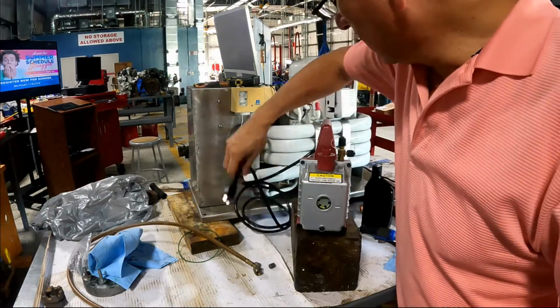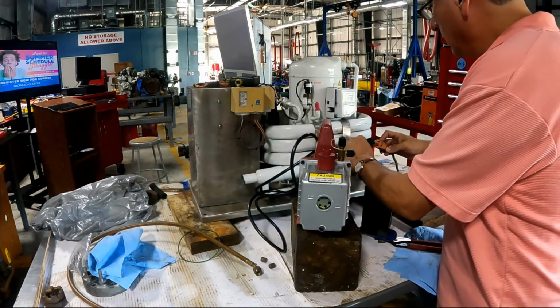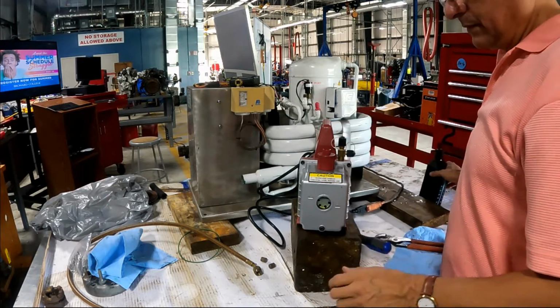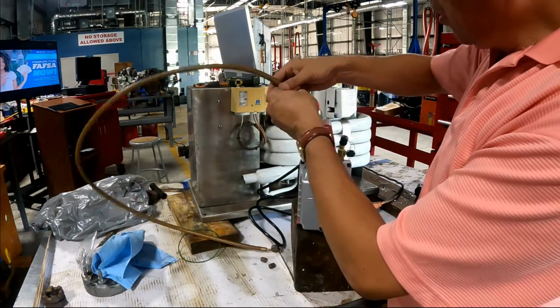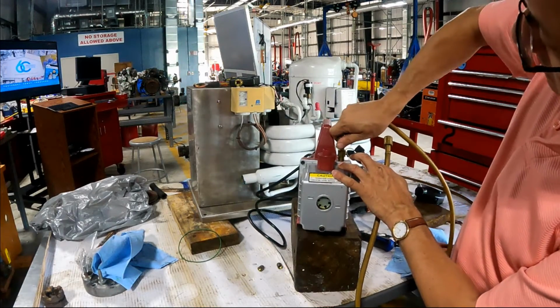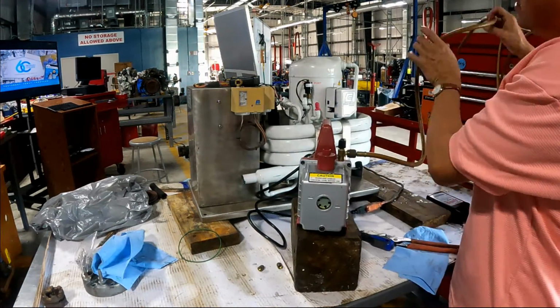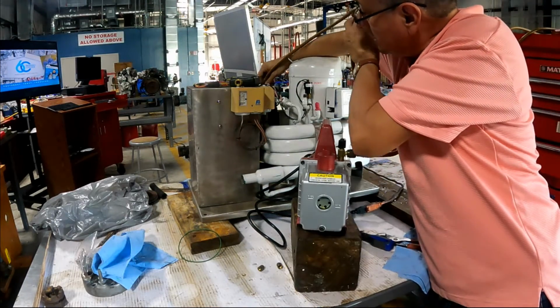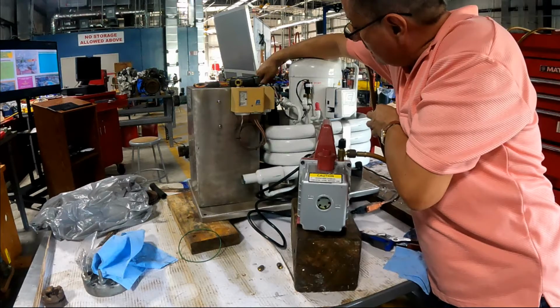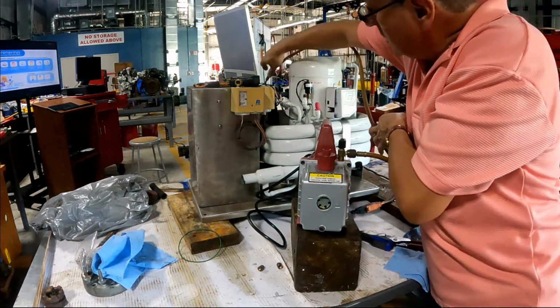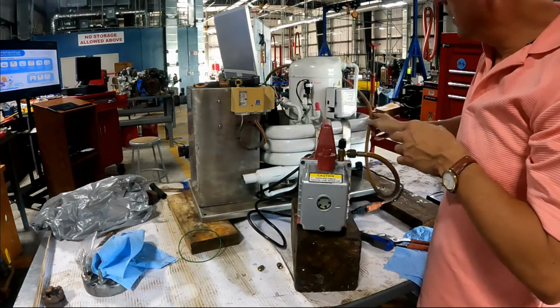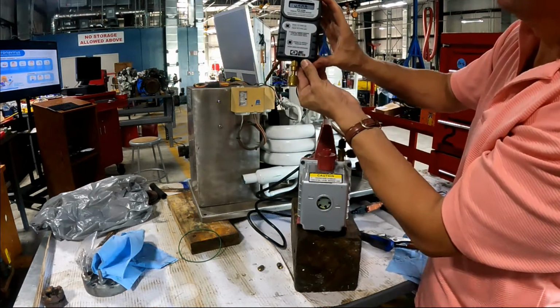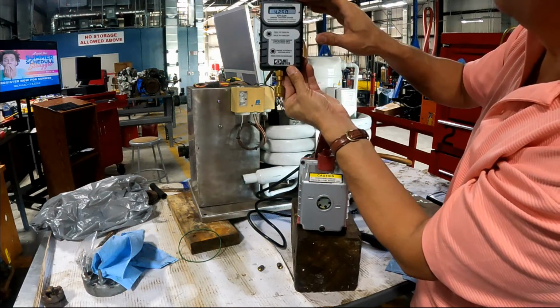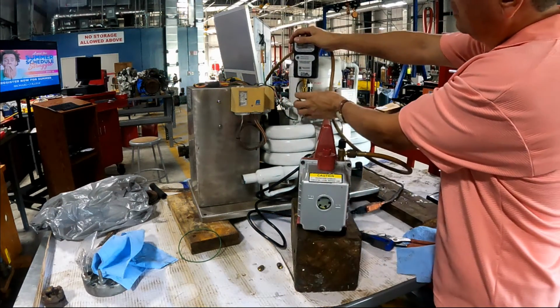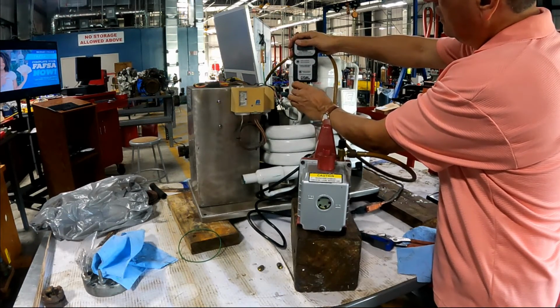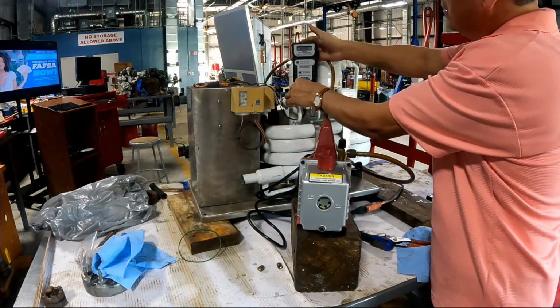We are ready. We are going to connect the pump properly. We are going to insert the hose. That's the hose, and we are going to put the hose on the low pressure side of the system. I prefer the low pressure side. And we are going to install the vacuum gauge. At this moment it is 4200, 4250 microns. And we are going to start the process.